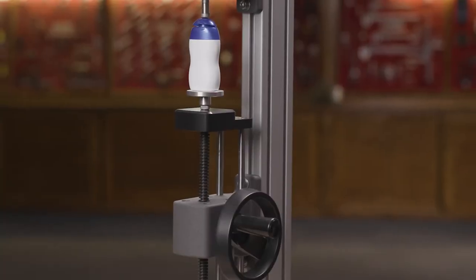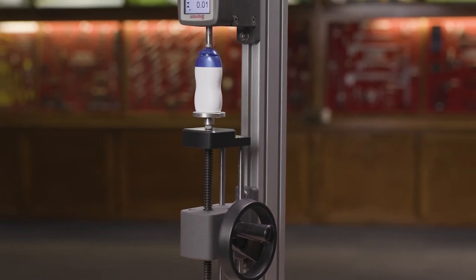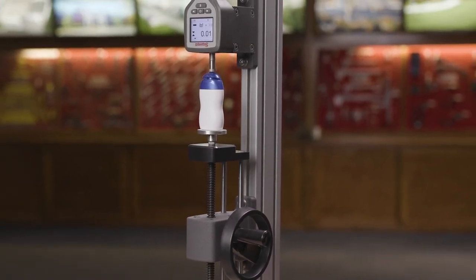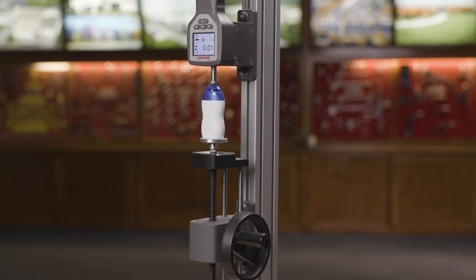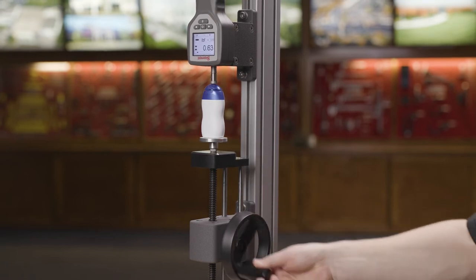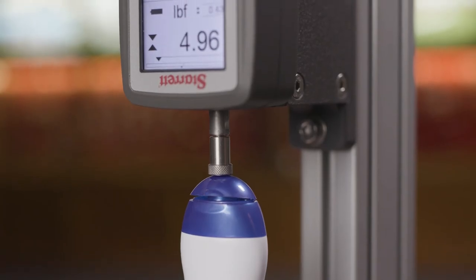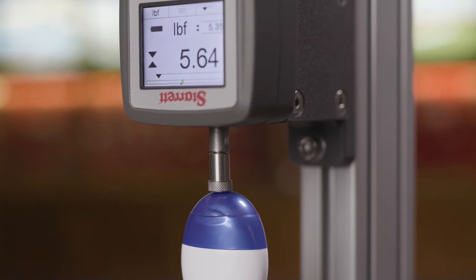The MTH manual tester offers a high resolution worm gear and hand wheel to make tests effortless and precise. One rotation of the hand wheel positions the crosshead .03 inches with a total range of four inches.